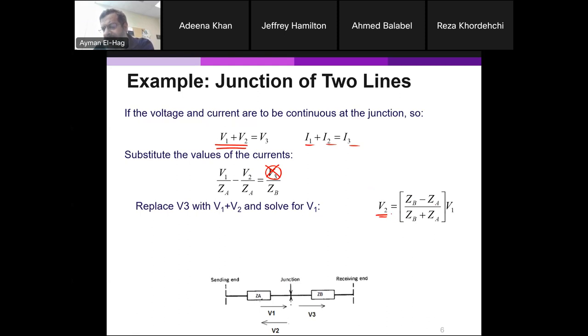And this is something very, very interesting here, because if the surge impedance of ZB is lower than ZA, then you will have a negative voltage. And this is very important. Why is that? Because let's say you have V1 coming with a positive polarity, the reflected wave will be added to it. So this is happening in a very short period of time. So if this is negative, then it will reduce basically the wave that's coming and reaches the joint. But if ZB is more than ZA, then the reflected wave will be positive and will be added to V1, which will make things worse.